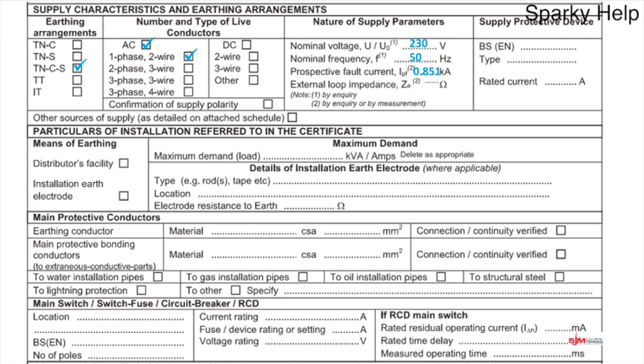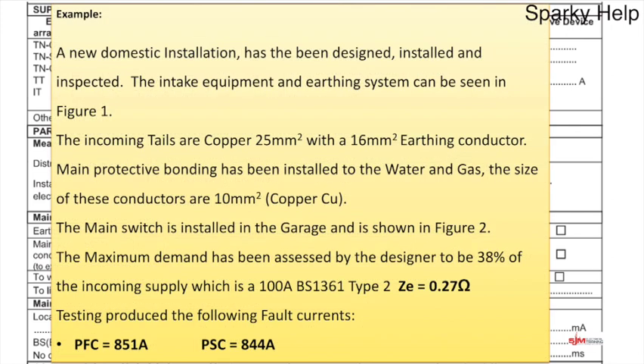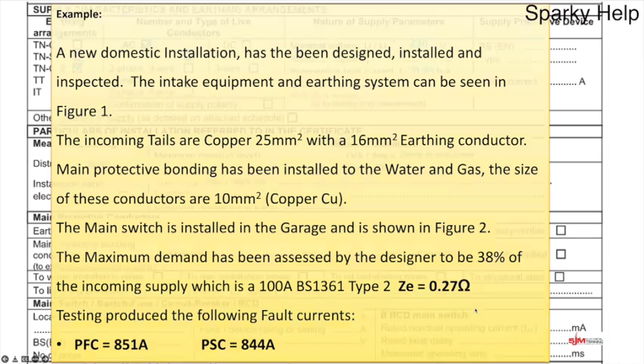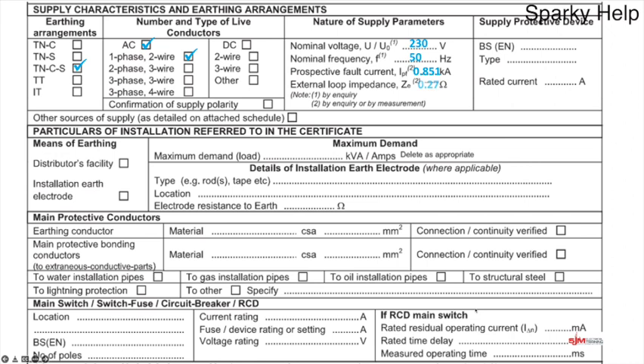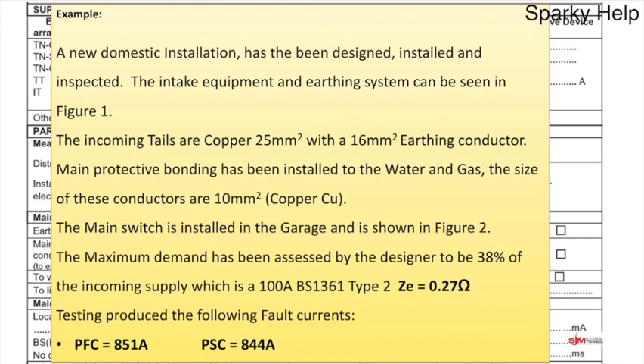So let's see what we've got. And on here, right at the bottom, we can see it says Ze is 0.27 of an ohm. So that is what we can put in: 0.27 of an ohm for our Ze. Ze, remember, is the line to earth value back to the star point of the transformer. Watch the video on how to do it if you're not sure.